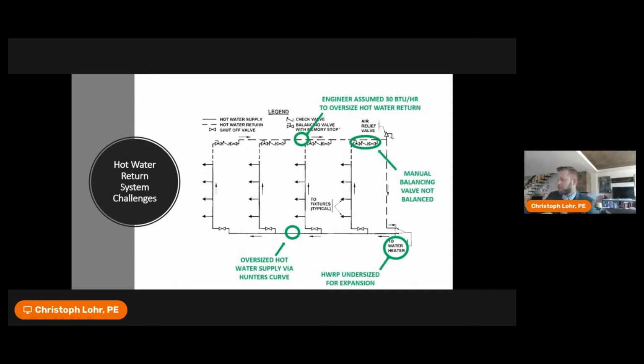So what are some of the issues? Well, we have the manual balancing valves not being balanced. I'm going to get my laser pointer here. We have manual balancing valves not being balanced. We have a hot water return pump. Sometimes that is undersized. We have hot water supply via the Hunter's curve in lieu of other design methodologies. And we have, in more cases than not, one of the biggest issues is a 30 BTU per hour assumption for the hot water return system in terms of BTU loss. And that is a really bad assumption. And I'll touch on that during our presentation here today.